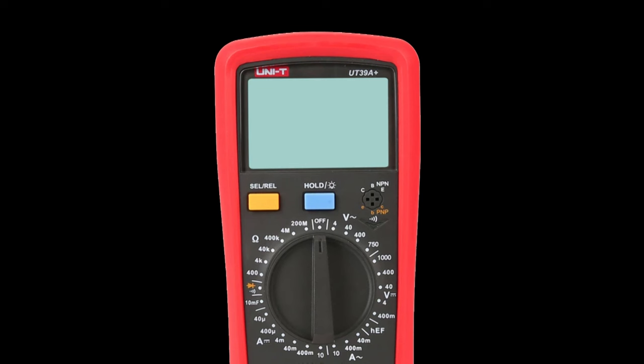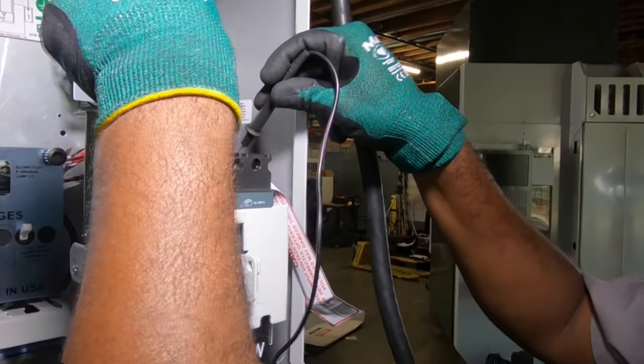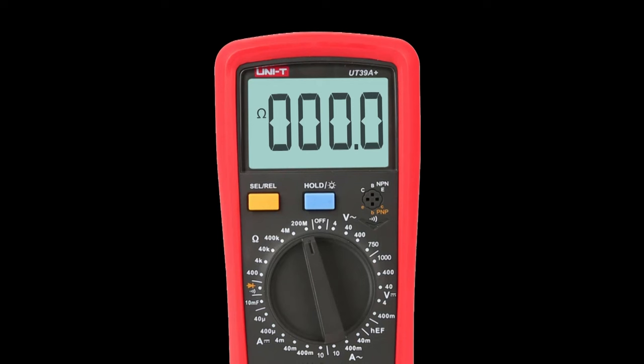Set the multimeter to the highest setting on the feature you're measuring, the highest voltage, amperage, or resistance. When you touch your probes, watch the display. If you don't get a valid reading, click the knob to the next lowest setting and test it again. If you don't get a valid reading, set the knob lower still. Keep going until you get a meaningful reading. To keep the reading, push the hold button, and the measurement will remain on the screen. When you're done with the meter, turn the knob to the off position.